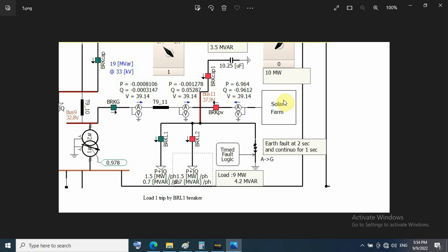Without the capacitor bank here, the voltage decreases to 30 kilovolts, so we cannot integrate because the voltage is out of limit.